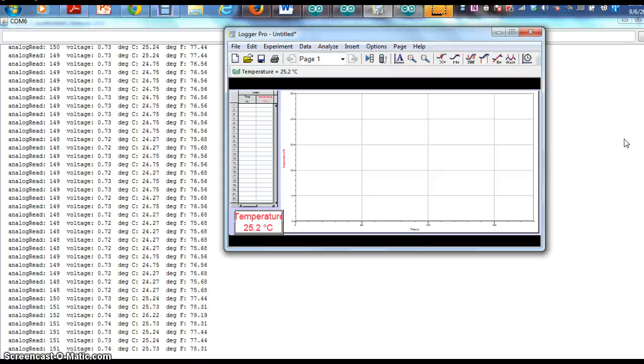All of the sensors that we're using, all the water sensors, all of the air sensors, have to be calibrated at some point. Some are very stable, like the temperature sensors, and you may not have to at all, at least this fall. Whereas when we go out in the field, the water quality sensors like pH need to be recalibrated, and our air quality sensors are definitely going to have some tricks about them that we're going to work through to get them to not just put out an analog value, but a value that reflects something we can really measure, such as parts per million. But at any rate, hopefully that gave you an idea of how sometimes you have to use a little math to make sure that your data has some meaningful accuracy.